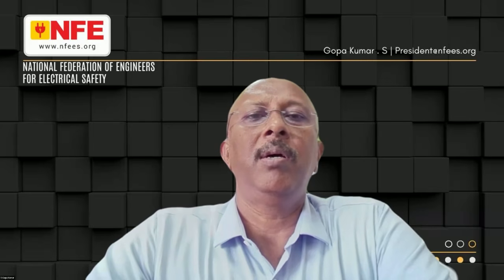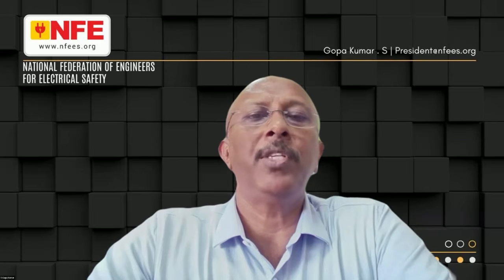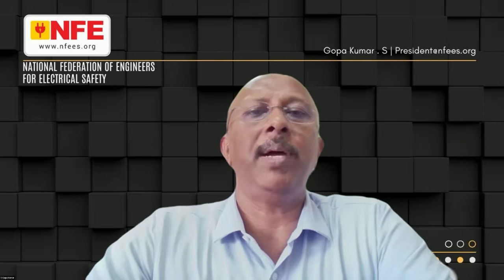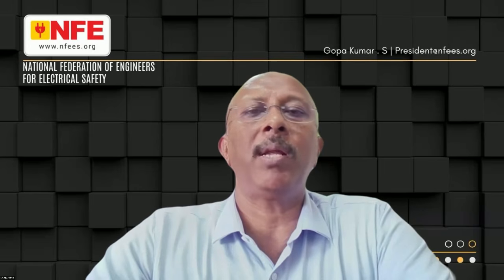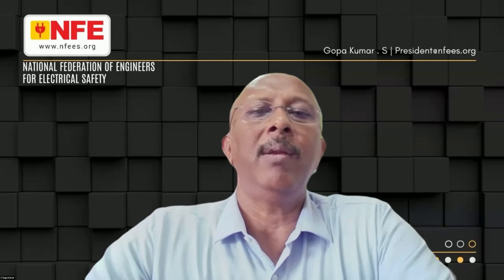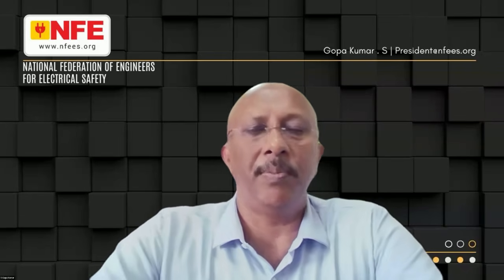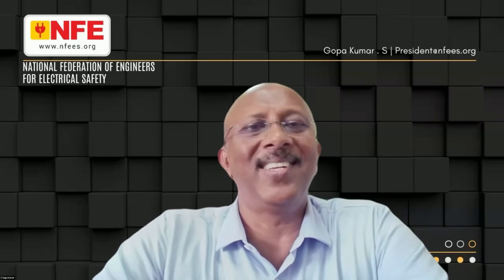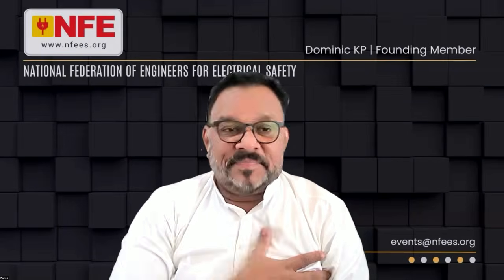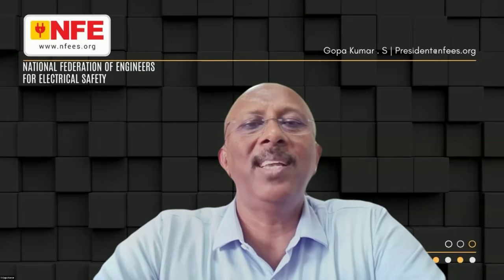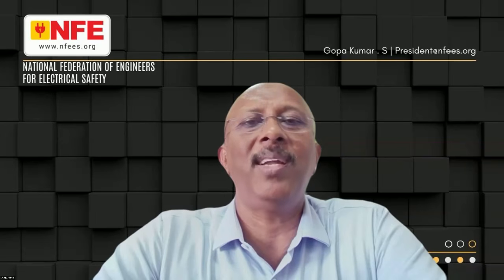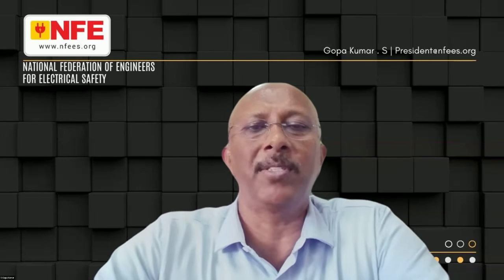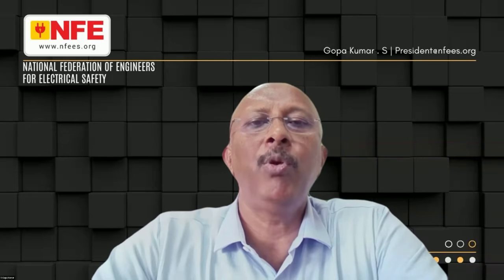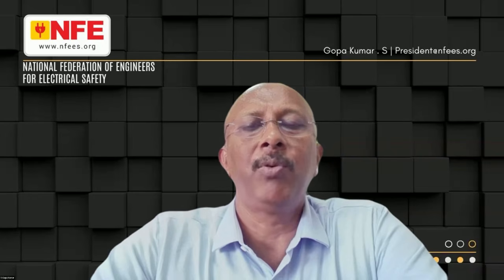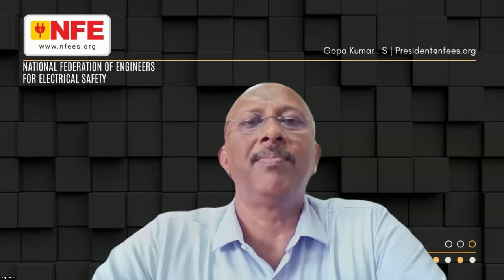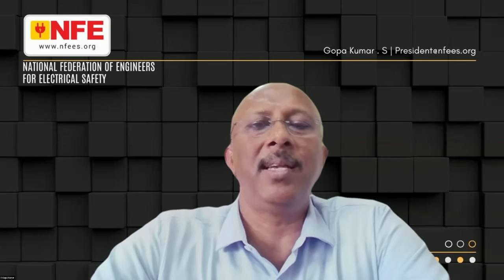There is a question: can there be any issue if medical staff uses UPS back to back, meaning supplying UPS power to another smaller capacity UPS and then to any load? Can it be a potential fire hazard or any other issue? This is a funny situation, especially in India. Actually, if you have a UPS, what is the need for putting another small UPS for additional backup? That means you don't rely on the first UPS. So the better way is to have two UPS with a fast changeover. Very fast changeover systems are also available. But sometimes this is a practice in India.